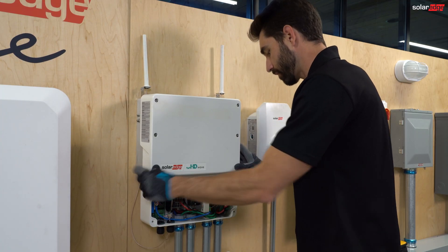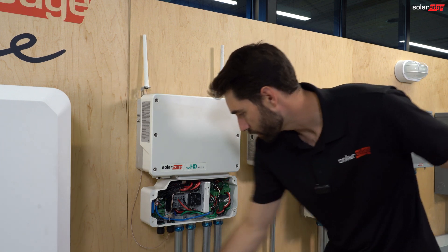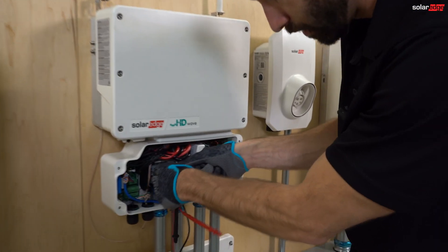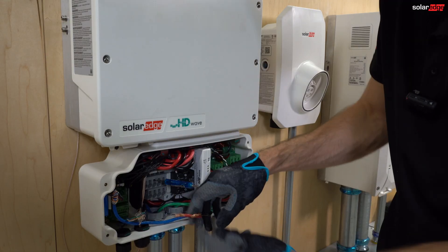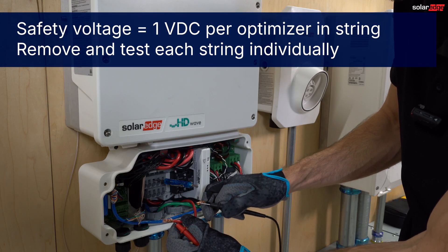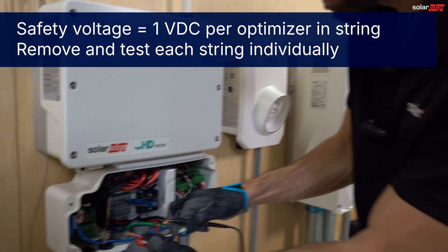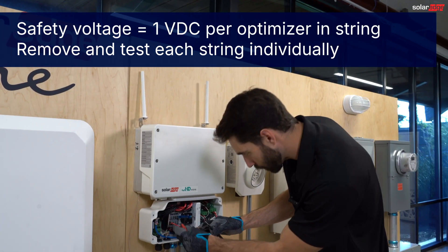We want to check our PV strings and open circuit voltage. To do that, we remove a positive and negative for each string and check our DC voltage there. Red to red, black to black. I've got 10 volts here and 10 optimizers, so that's great. I'm going to put that back.